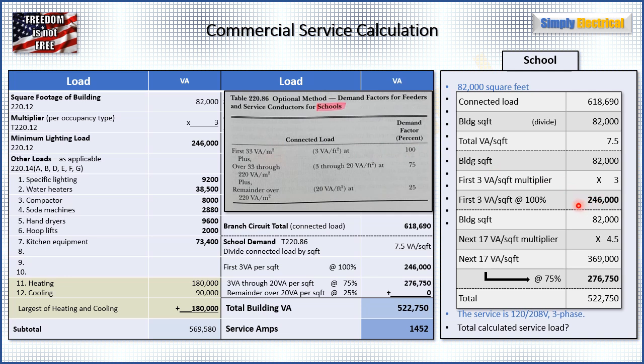For the second line, we cover 3 through 20 VA per square foot at 75%. We had 7.5 total; we already used the first 3, leaving 4.5. Multiply 4.5 by 82,000 and get 369,000 VA. Taking 75% of that gives 276,750 VA. Adding the two bold numbers together — 246,000 plus 276,750 — gives a total building VA of 522,750. We shaved off almost 100,000 VA using this demand factor, which represents substantial savings in wire, conduit, and labor.